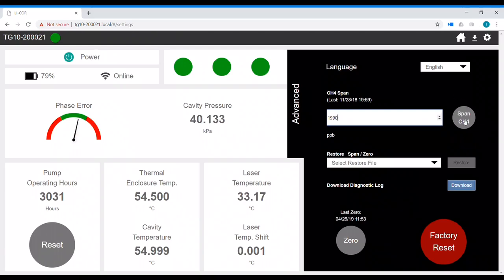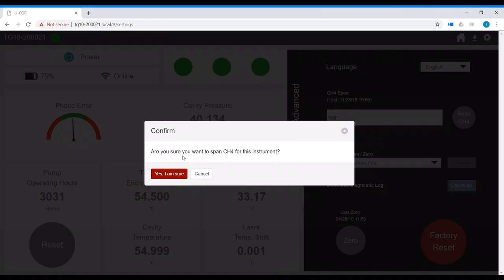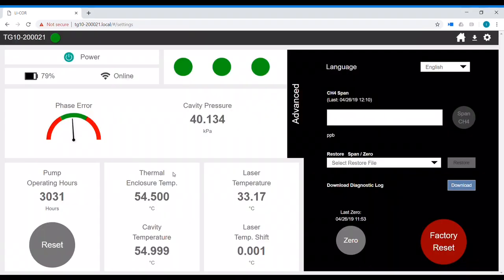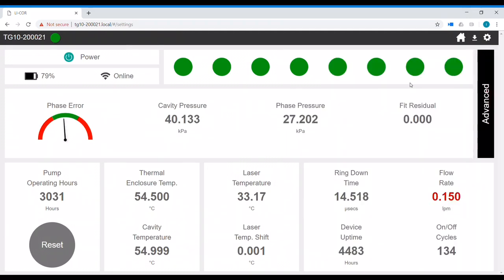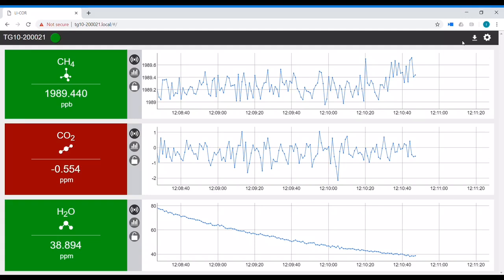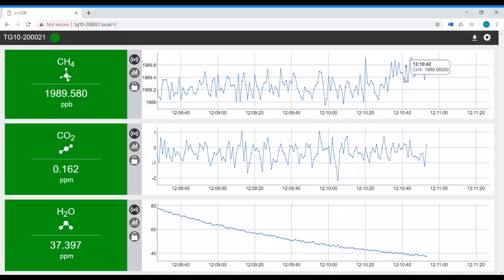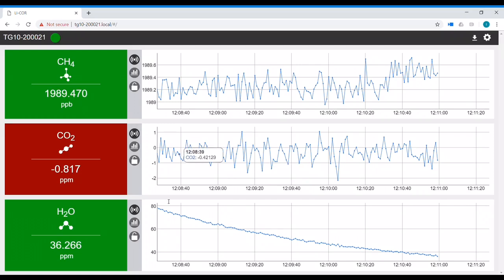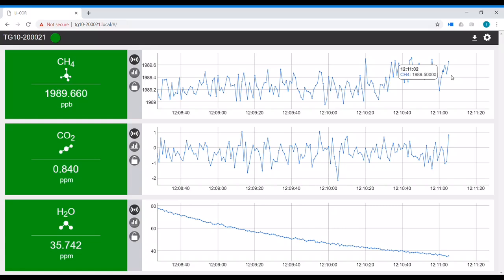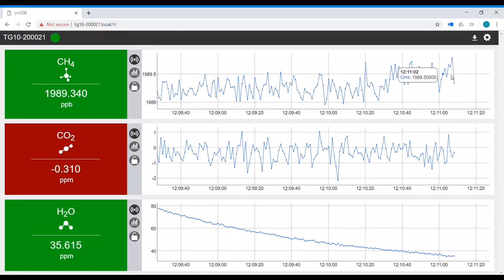We'll go ahead and click span. It will ask, are you sure you want to span CH4 for this instrument? Yes, I'm sure. And that's it for span. There's no wait. It quickly takes the readings and calculates the multiplier, and that multiplier is now going to be applied for CO2, water, and methane. Because we were already right at the same point, there's not a noticeable step change. There is a small change, but nothing noticeable. And the CO2 and water readings are also adjusted by the same amount. And that's how we do zero and span calibration on the LI-7810.